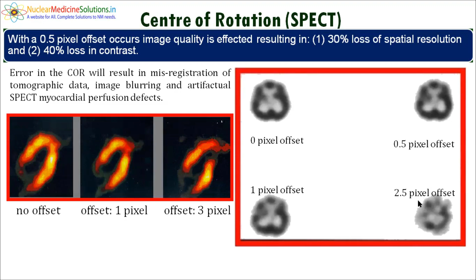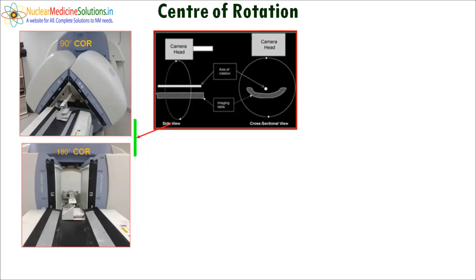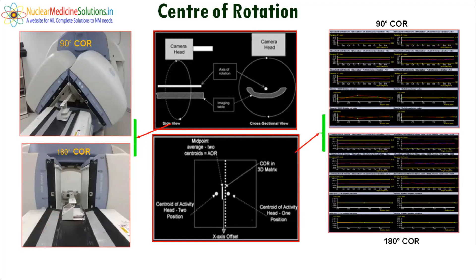The center of rotation test can be performed by using a point source, and we are doing a COR test for both 90 and 180 degrees. Now we'll discuss the misregistration and how it affects your image quality. Problems in the misregistration or co-registration in SPECT and CT are common and can be due to a system error or caused by movement of the patient.